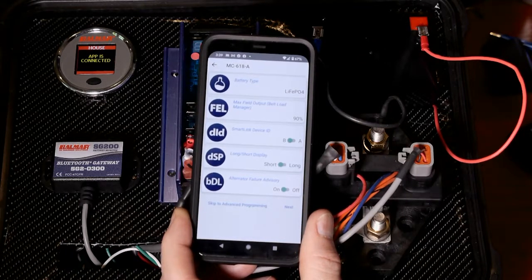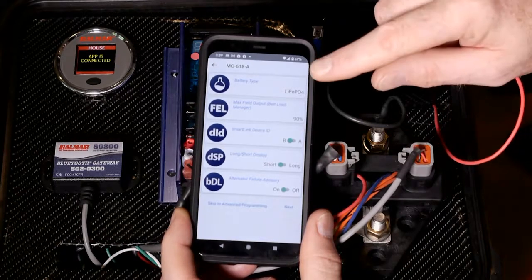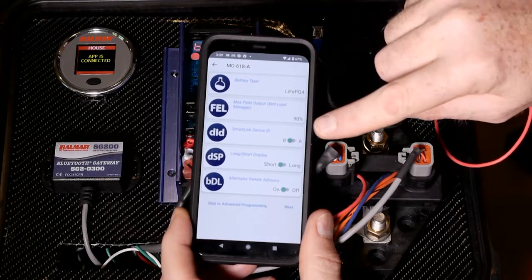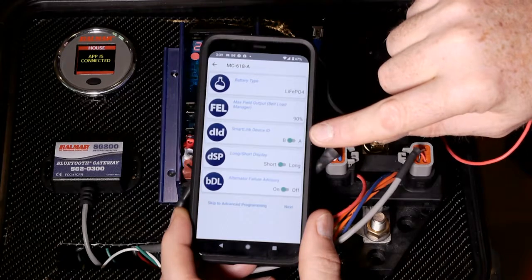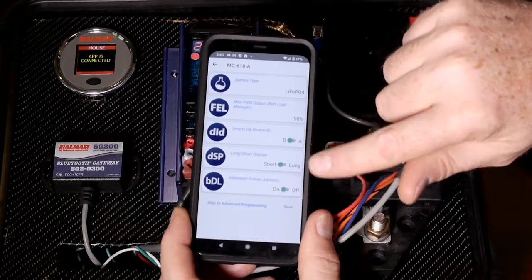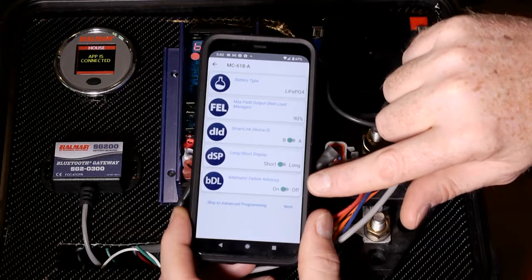If I want to program, I'm going to hit the three-bar menu, click on settings, and this will give you an overview of the basic settings available to program on the regulator in basic mode: battery type, field output max, SmartLink ID — so if you've got a two-regulator system, you can change one to A or B — and then change the display and advisory information shown on the display.